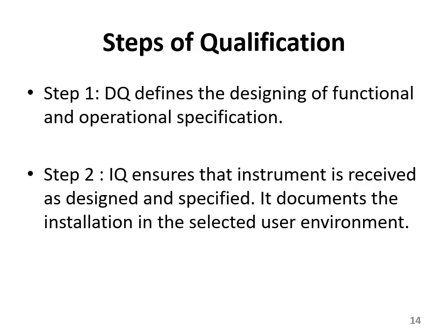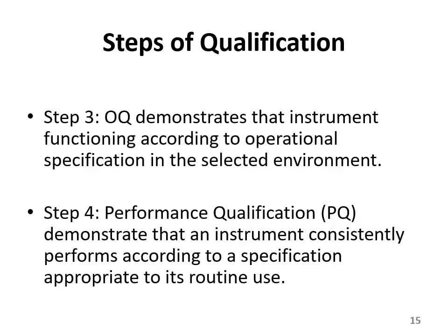Step 3, operational qualification. Okay, demonstrate that a balance or instrument will function according to its operational specification in the selected environment. We have discussed it. Step 4, performance qualification, PQ, demonstrate that an instrument is consistently performing according to a specification appropriate to its routine use.